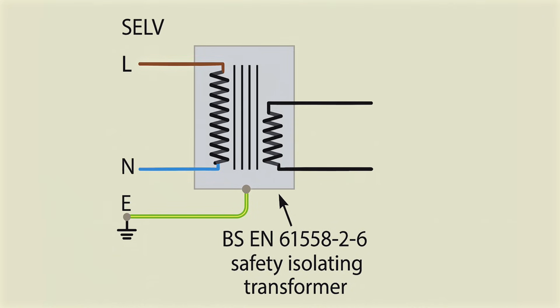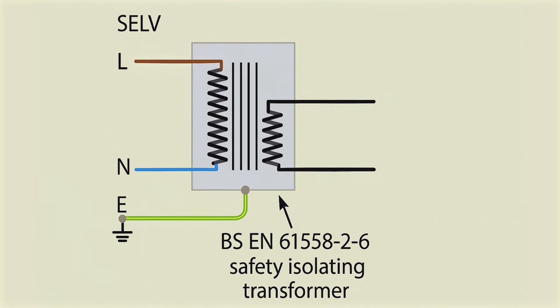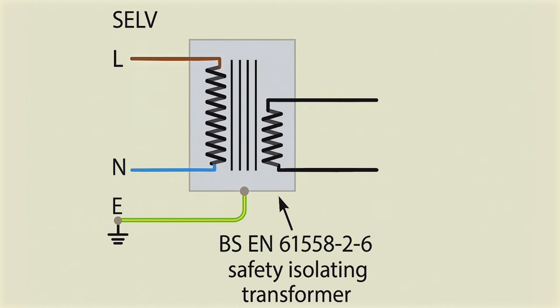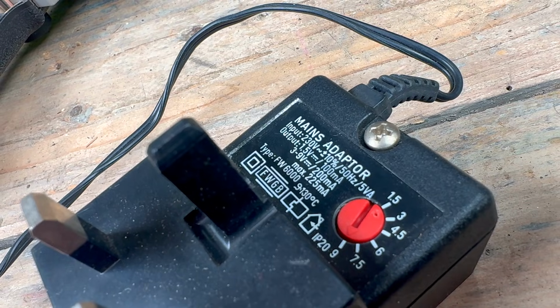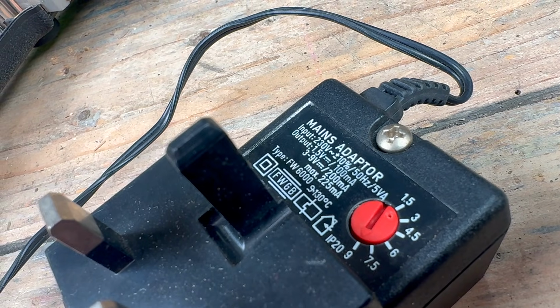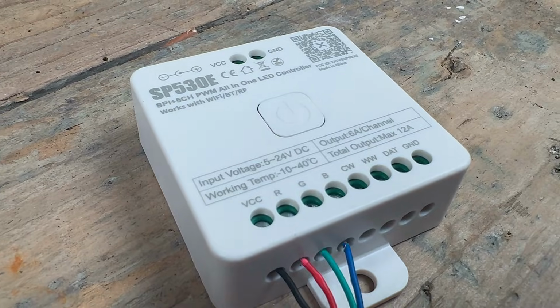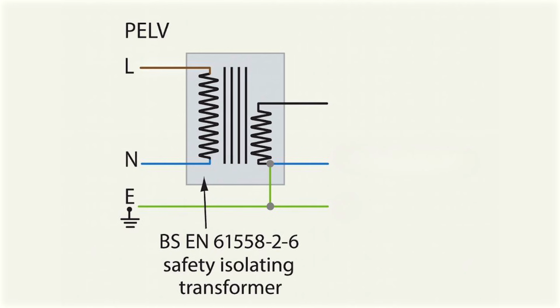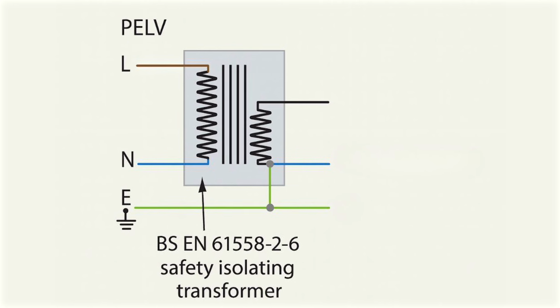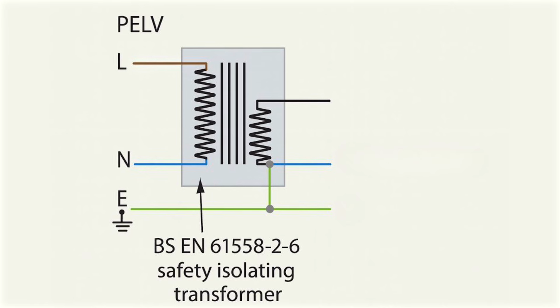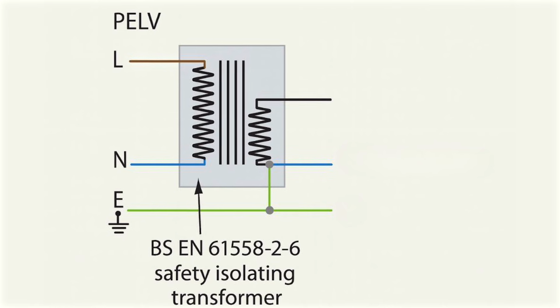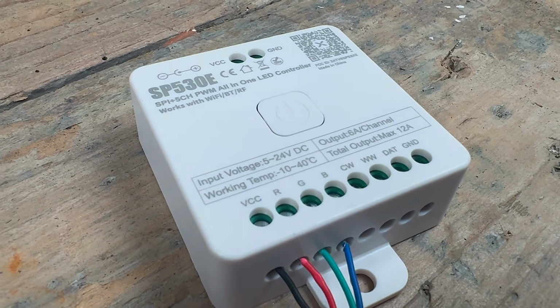There is no return path, and that is the protective principle. So the most common Class 3 arrangements are SELV and PELV. SELV, separated extra low voltage, uses extra low voltage supplied from a source that is electrically separated from earth. This is the safest configuration because even simultaneous contact with earth cannot cause a dangerous shock. PELV, protected extra low voltage, also uses extra low voltage, but the system may be earthed at one point for functional reasons. Both SELV and PELV appear in LED drivers, control circuits, chargers, and toys.